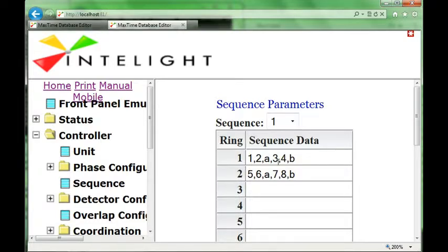So I cannot go in there and delete phases 3 and 4. I cannot have an A comma B comma with no phase in there. It can be any phase. It doesn't have to have an output. It doesn't have to have timing in it. It could be a dummy phase like 9 comma B, that's legal, or 39. It just cannot be something between it. You cannot have A comma blank and leave the B off.